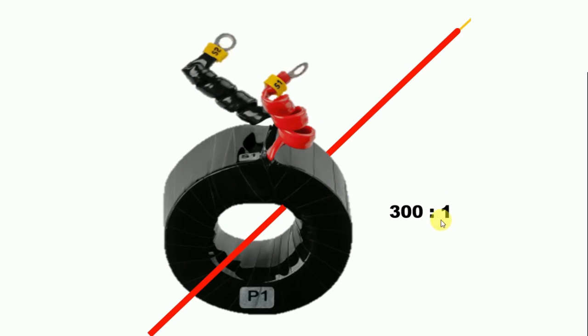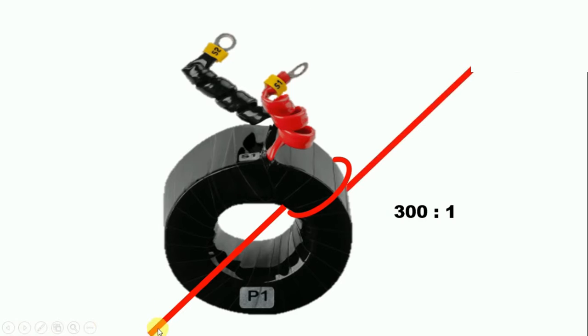Look here, now we have to change the ratio of this CT. What we do is take the wire and wrap it once around the CT in this way. You can see the wire goes from here, wraps around the CT, and from inside goes out. It means there is only one turn.